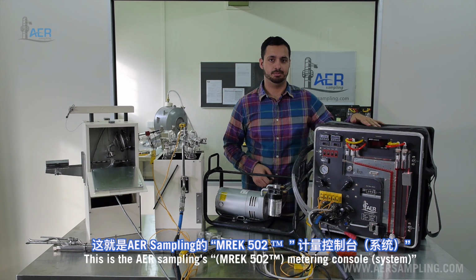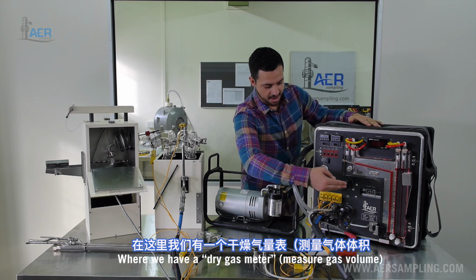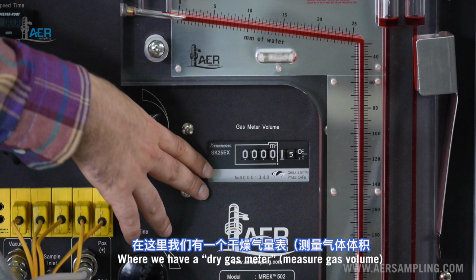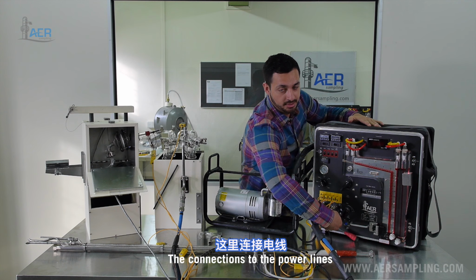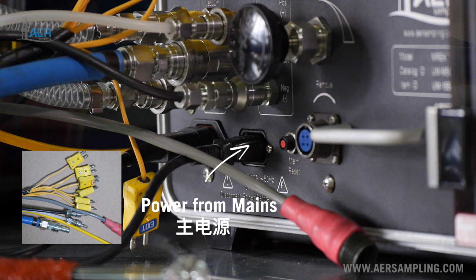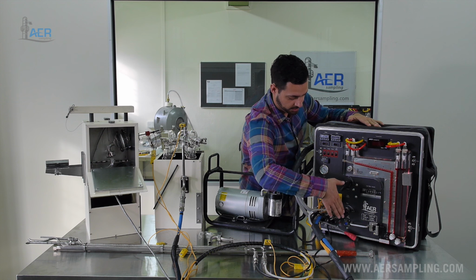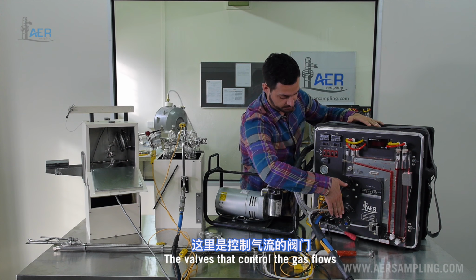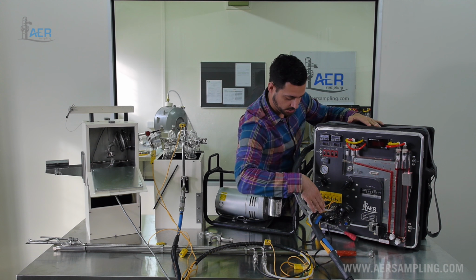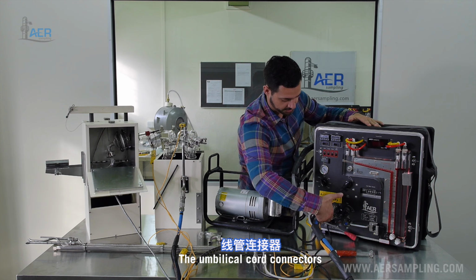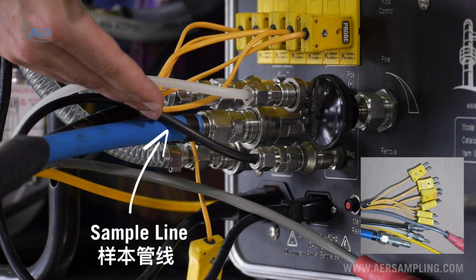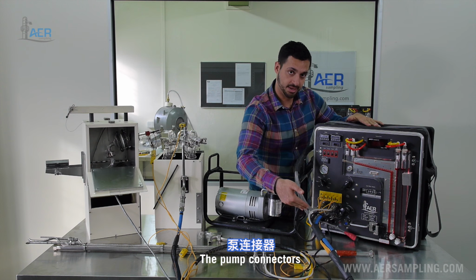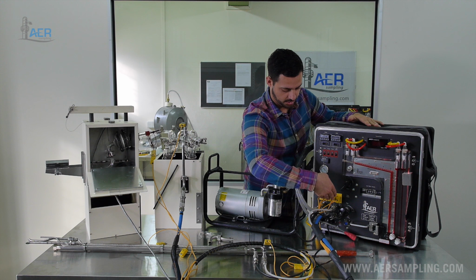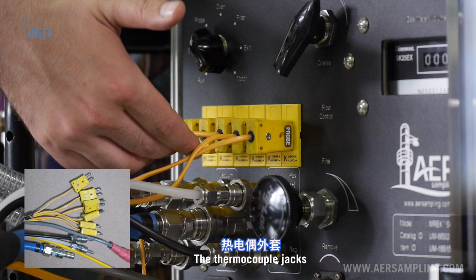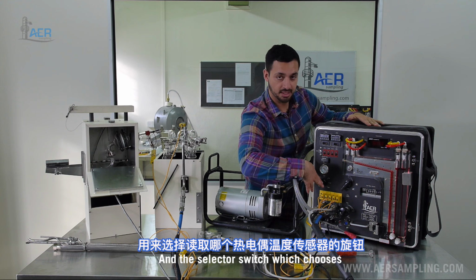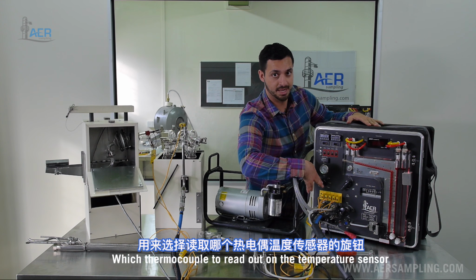This is Aer Sampling's metering console, where we have a dry gas meter, the connections to the power lines, the valves that control the gas flow, the umbilical cord connections, the pump connections, the thermocouple jacks, and the selector switch, which chooses which thermocouple to read out on the temperature sensor.